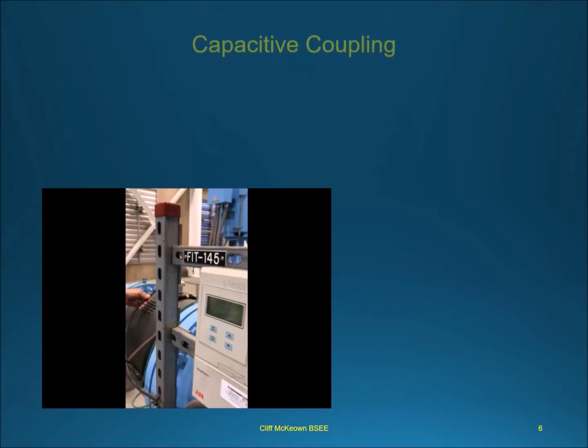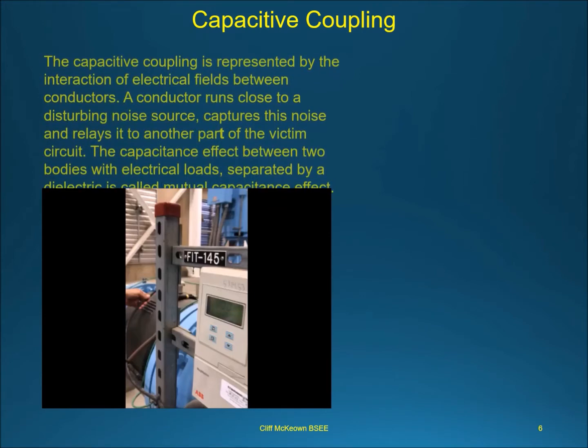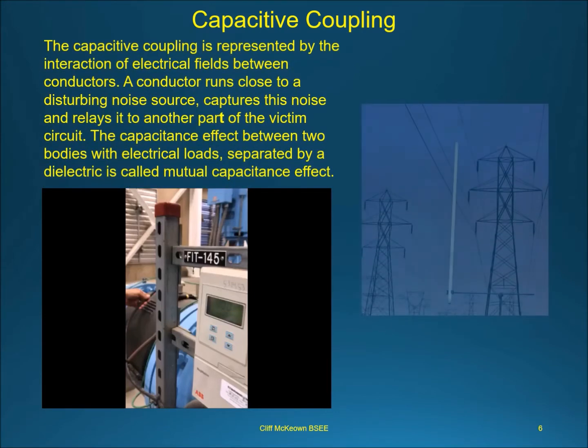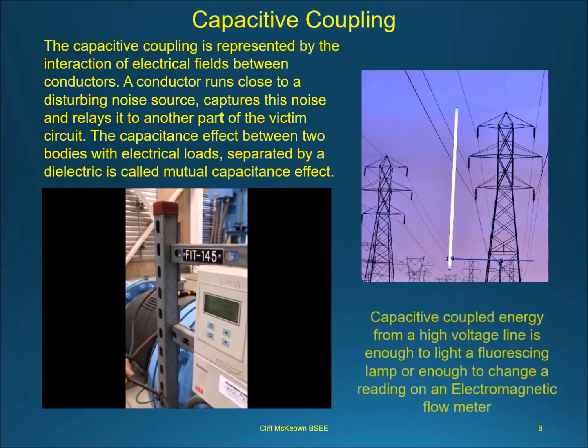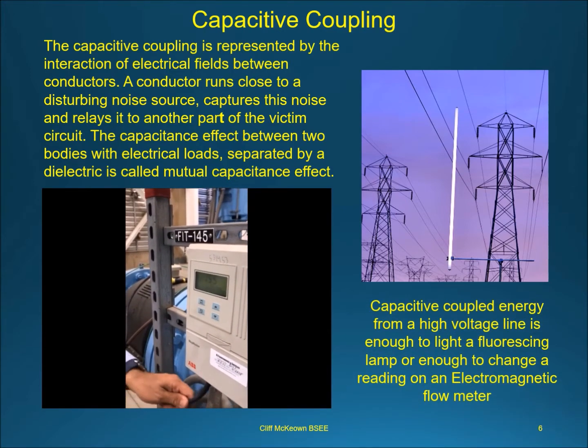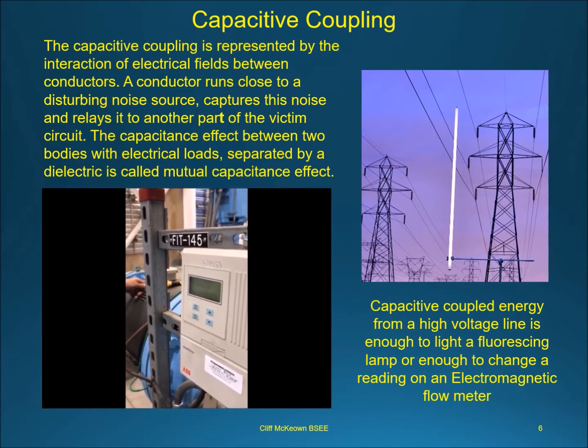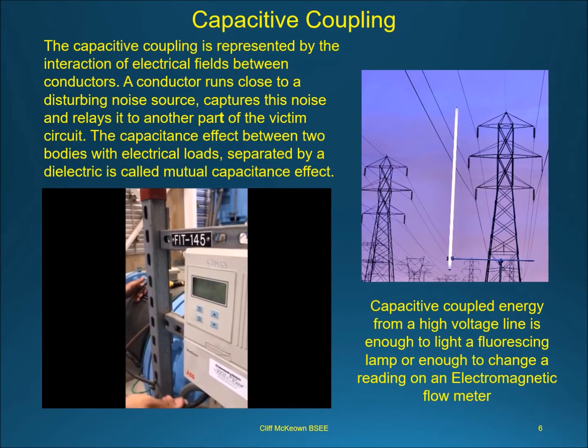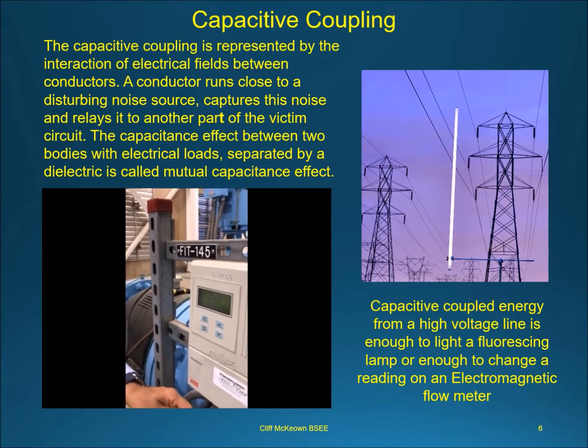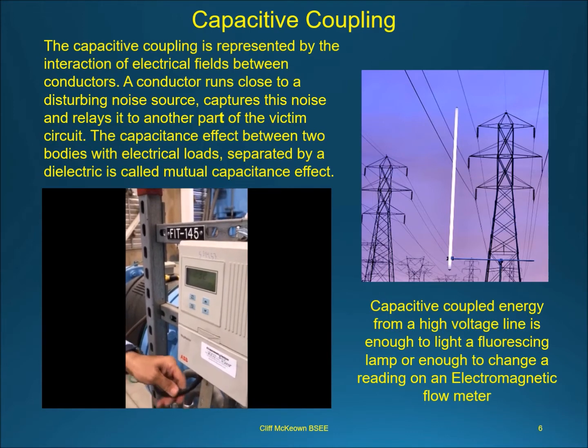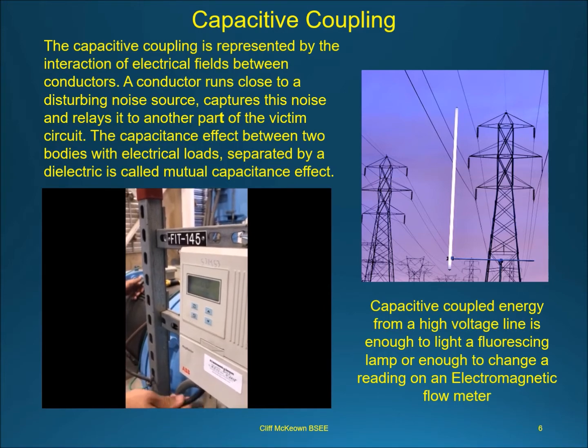Capacitive coupling is represented by the interaction of electrical fields between conductors. A conductor runs close to a disturbing noise source, captures this noise and relays it to another part of the victim circuit. The capacitance effect between two bodies with electrical loads, separated by a dielectric, is called the mutual capacitance effect. Capacitive coupled energy from a high voltage line is enough to light a fluorescent lamp. The effect of coupling can be seen in this video where simply moving the flow tube signal cable causes the coupling to increase or decrease, causing a shift in reading.